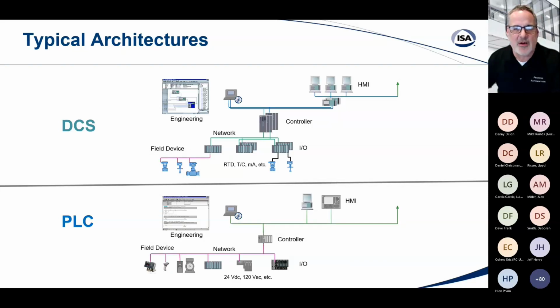And then, of course, the networks. Again, on the DCS side, inherently, these are all built based on redundant concepts. So everything that connects the signal from the field all the way up to the HMI, there shall be no single point of failure. Of course, you can minimize it and save some money by not going with redundancy, but the system was built based on redundancy versus the PLC side. It was built on simplex concepts, or singular concepts, and they added on some redundancy concepts for those high availability requirements.